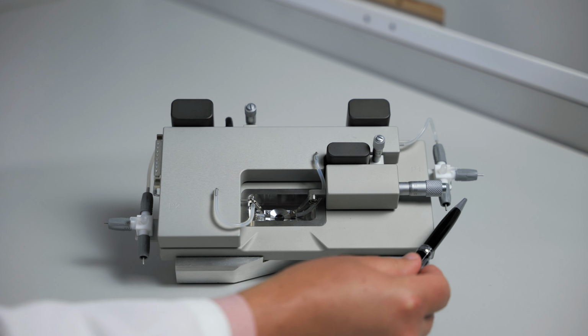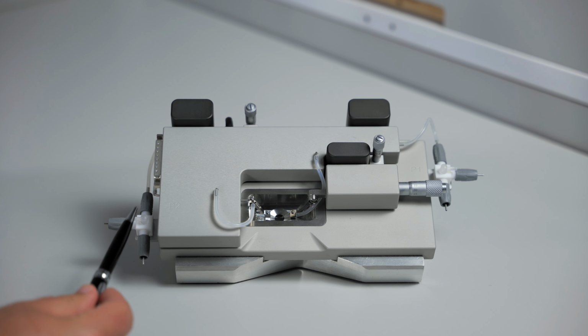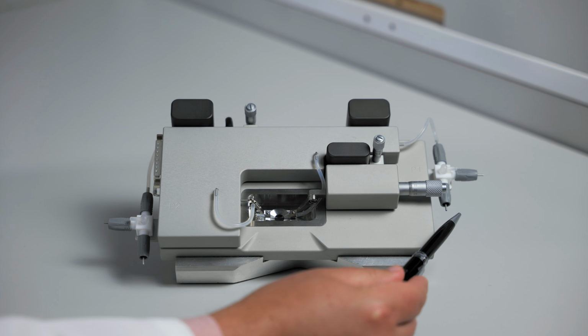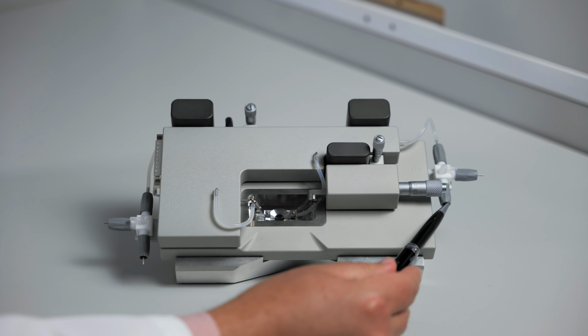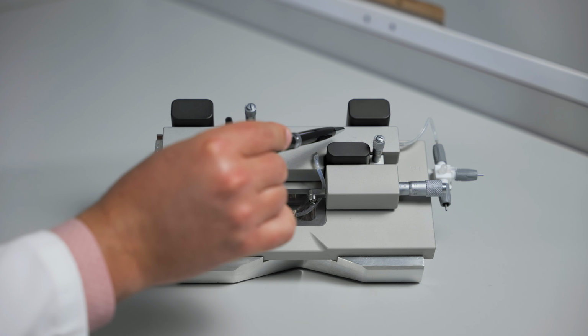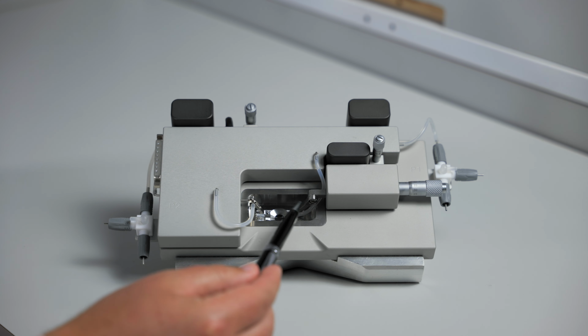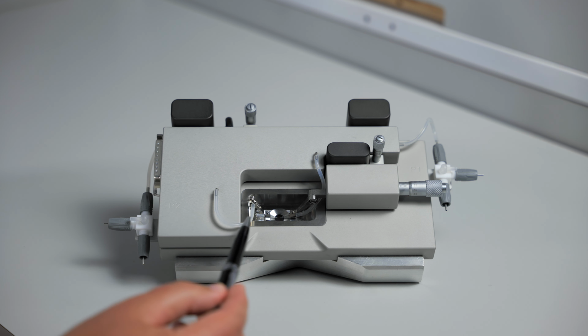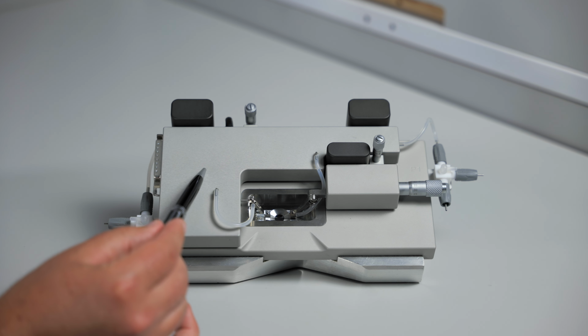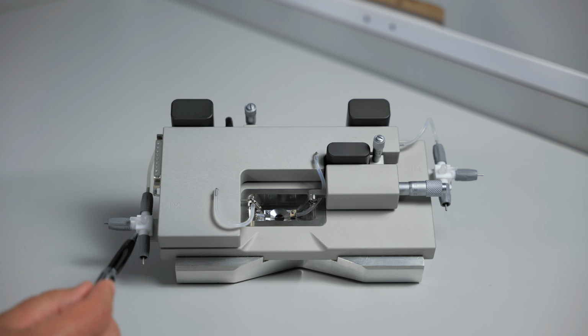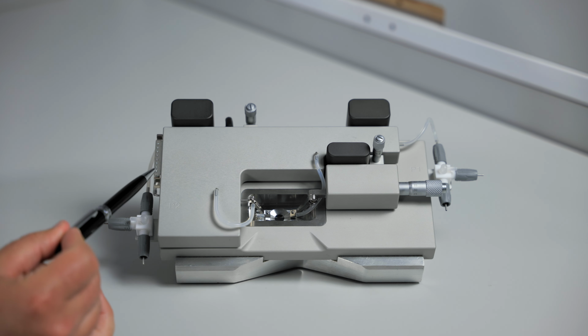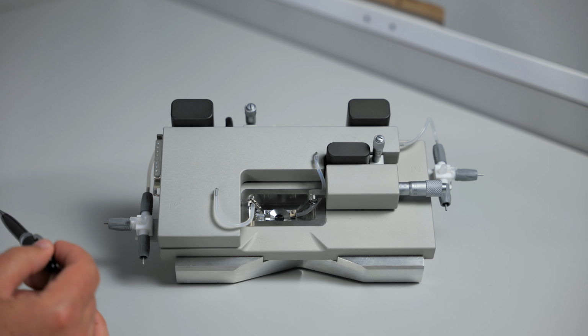There's a 3-way valve on either side of your chamber. Pressure and buffer will enter through the P1 3-way valve, go through a pressure transducer, and enter the vessel and your chamber. The pressure will then leave the vessel, go through the tubing into a second pressure transducer, and exit the chamber through the P2 3-way valve. There's a connection for the myograph cable, which will go to the interface.